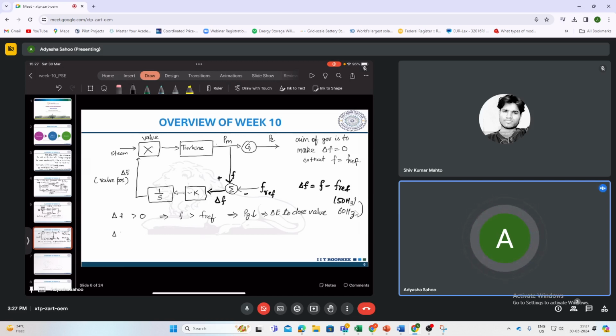And similarly, if delta F is less than 0, which means that your F is less than the reference frequency, that means you need to increase the output of the generator. So it will give the signal to open the gates or the valve to maintain the frequency equal to the reference frequency always.